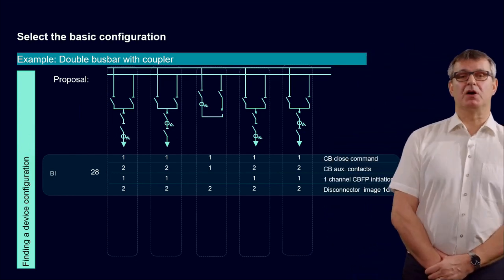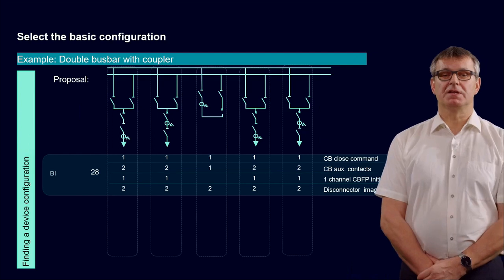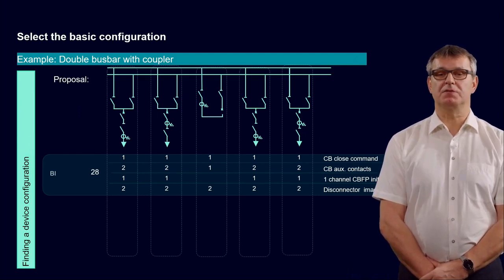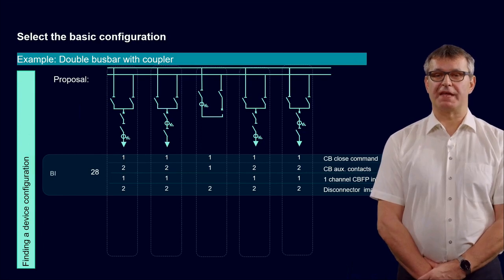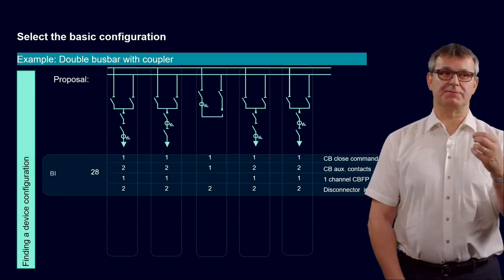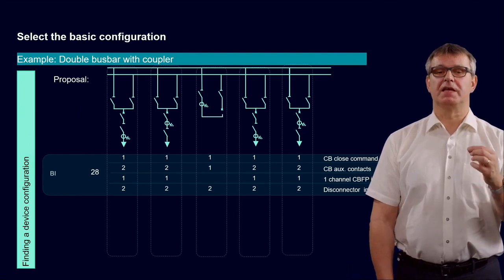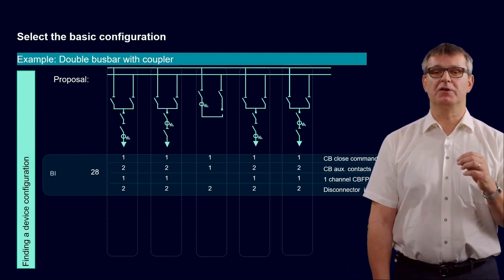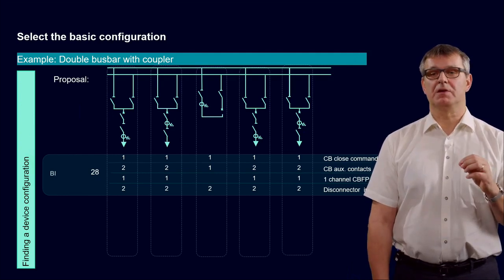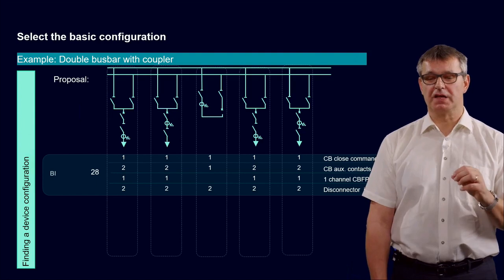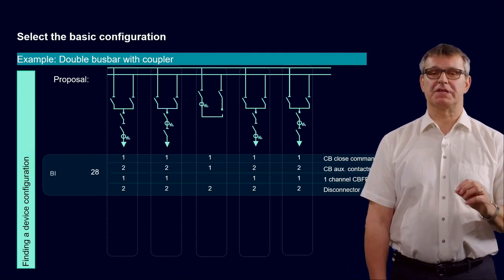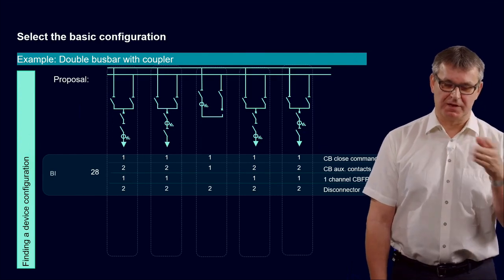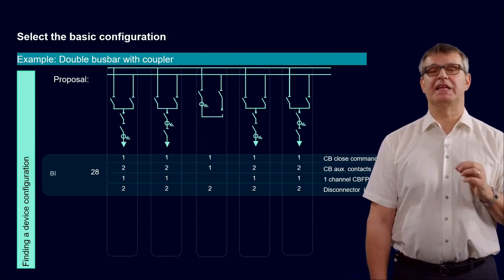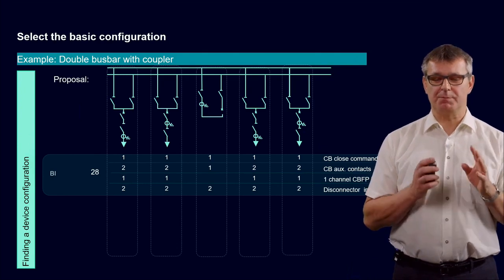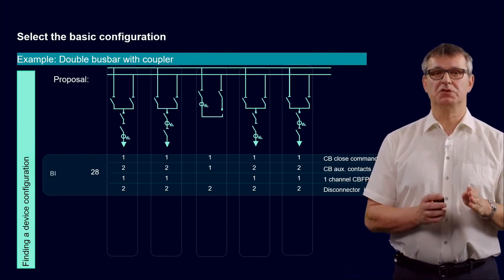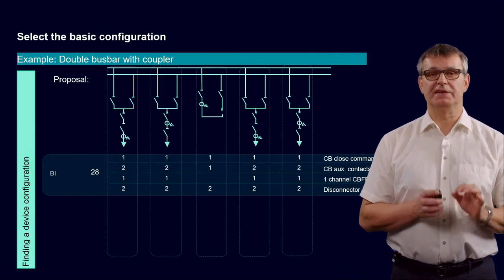Let's count the number of necessary binary inputs. So what binary inputs do we need? We need the circuit breaker close command. That's very essential and important for the end-fault protection to bring really right in time, when the circuit breaker is closed, the current back to the measurement system. So that's very essential. Once again, it will be explained in more detail together with the end-fault protection. But really, it's very important not to forget to use the circuit breaker close command for the end-fault protection.